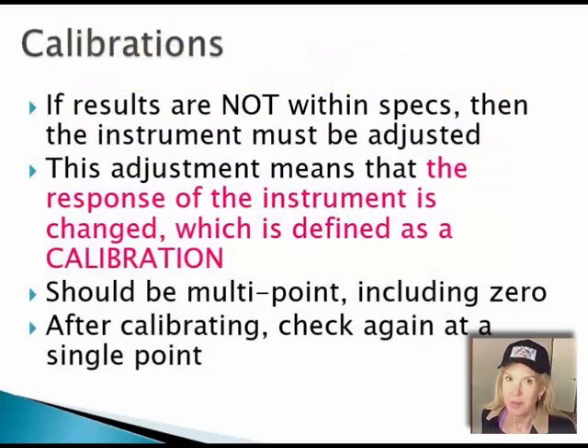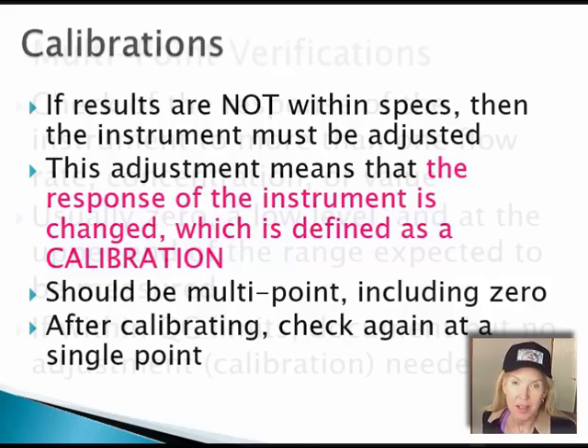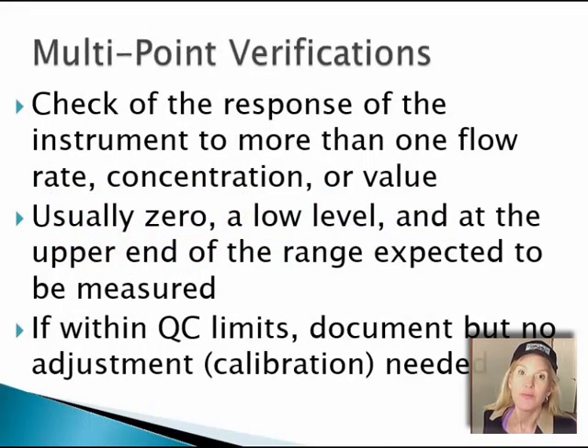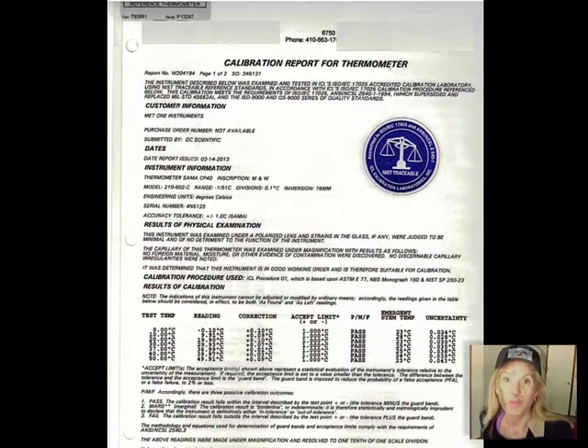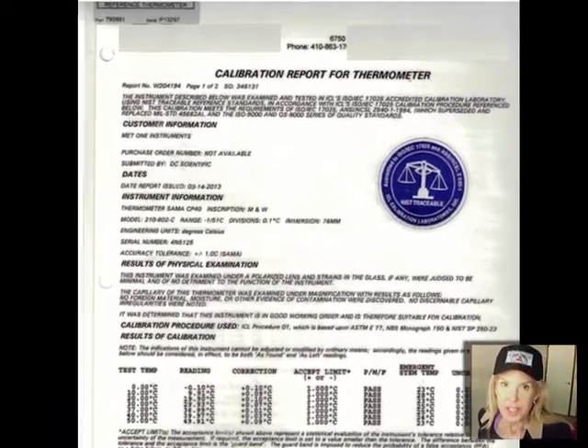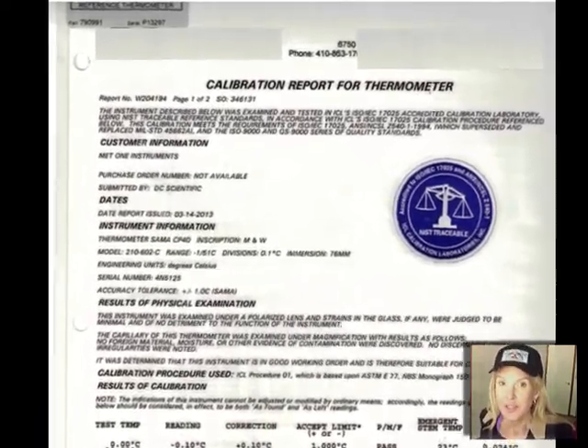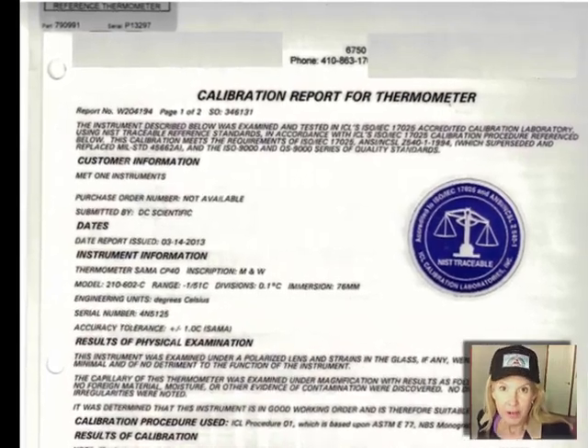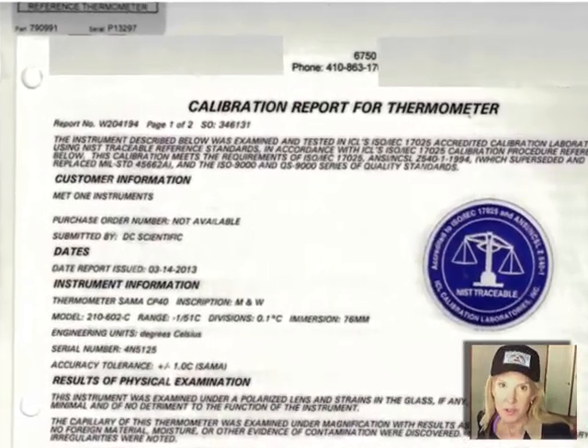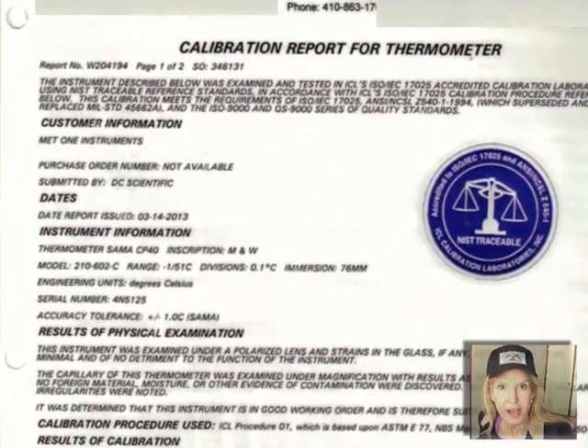Calibration. Calibration is when you actually make an adjustment to the instrument that you're using to make measurements with. Verification is when you verify that the instrument is operating within the limits. Another term is certification. Usually that's talking about getting a certificate from the manufacturer of your transfer standards or wherever you get them recalibrated.